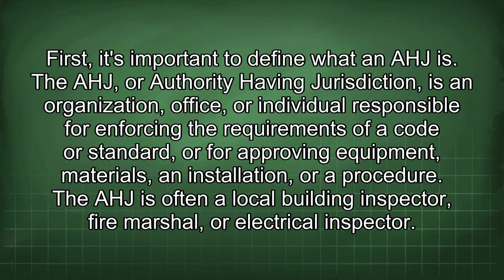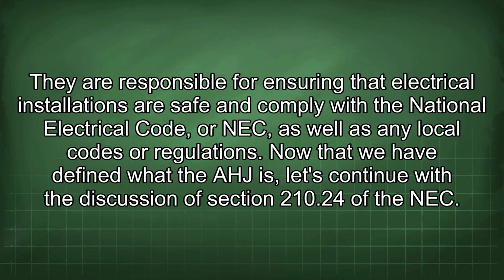First, it's important to define what an AHJ is. The AHJ, or authority having jurisdiction, is an organization, office, or individual responsible for enforcing the requirements of a code or standard, or for approving equipment, materials, an installation, or a procedure. The AHJ is often a local building inspector, fire marshal, or electrical inspector. They are responsible for ensuring that electrical installations are safe and comply with the National Electrical Code, or NEC, as well as any local codes or regulations. Now that we have defined what the AHJ is, let's continue with the discussion of Section 210.24 of the NEC.